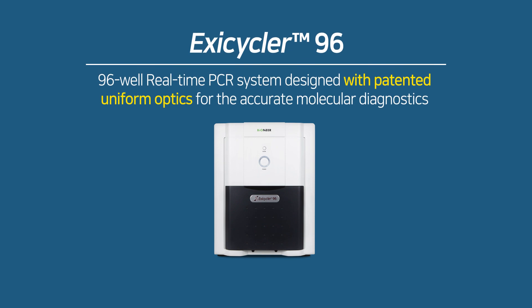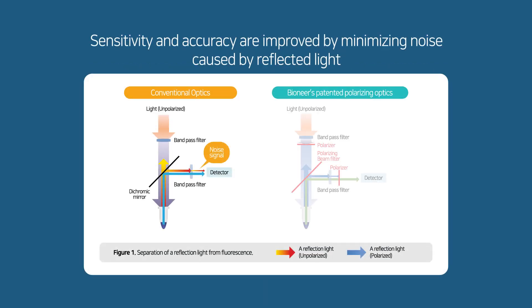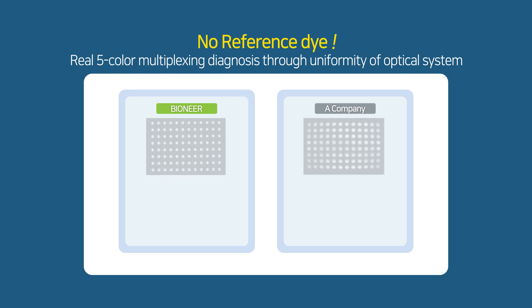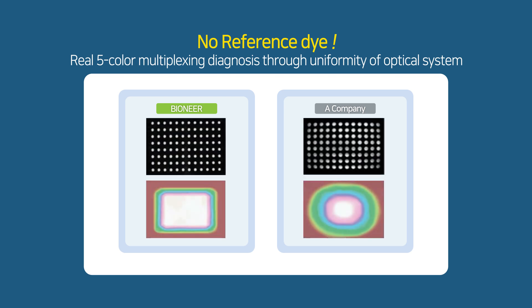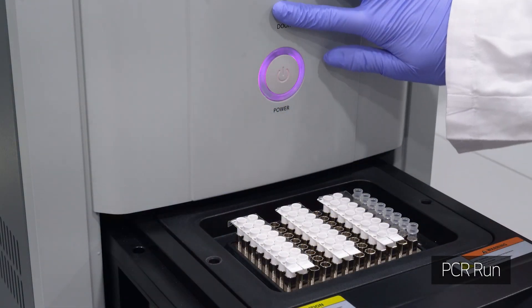Exicycler 96 is a real-time PCR thermocycler that performs molecular diagnosis by amplifying extracted nucleic acids. We have improved sensitivity and accuracy through our own patented technology by minimizing noise caused by reflected light. It can perform complete five-channel multiplex testing without the need for reference dye, with a uniform optical system.